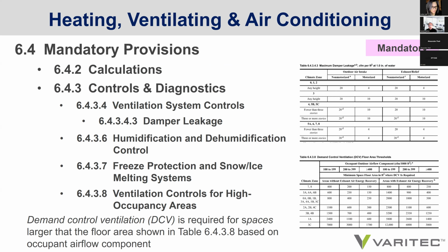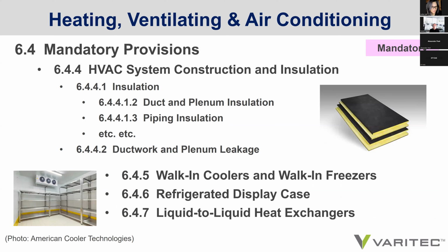There's also mandatory language on calculations, controls, and diagnostics for ventilation system controls. There's language on damper leakage, humidification and dehumidification control, freeze protection, and snow ice melting systems. Not that we should probably need that in Phoenix, Arizona so much, but also on ventilation controls for high occupancy areas. There's mandatory language on insulation, duct and plenum insulation, piping insulation, etc., as well as walk-in coolers, walk-in freezers, refrigerated display cases, liquid-to-liquid heat exchangers, etc.